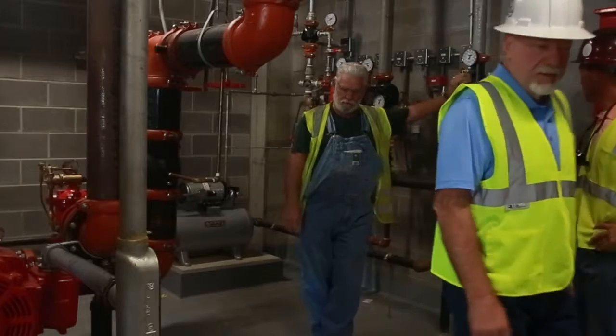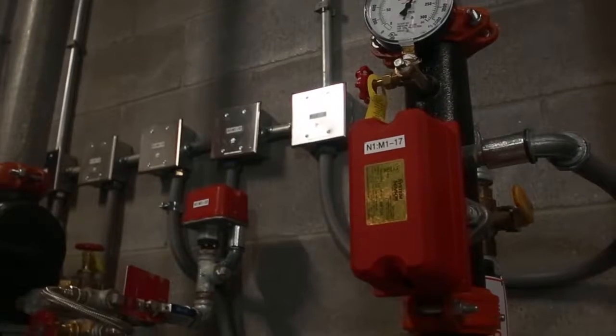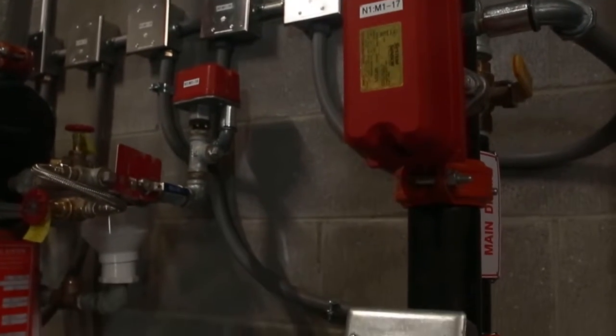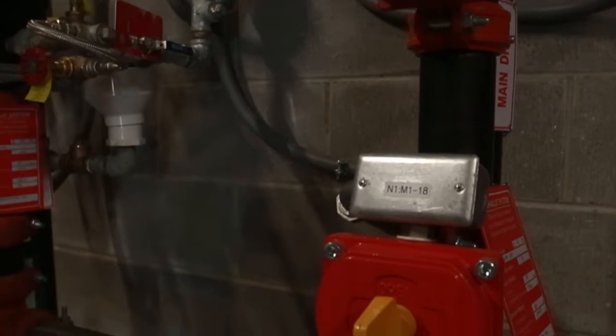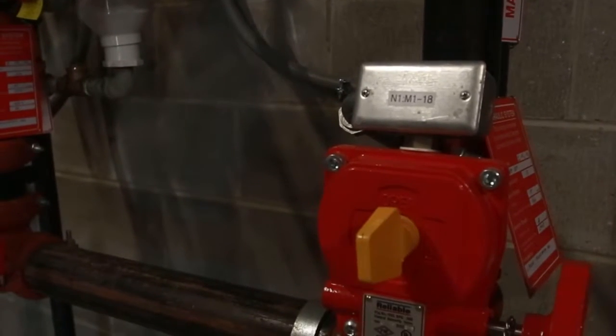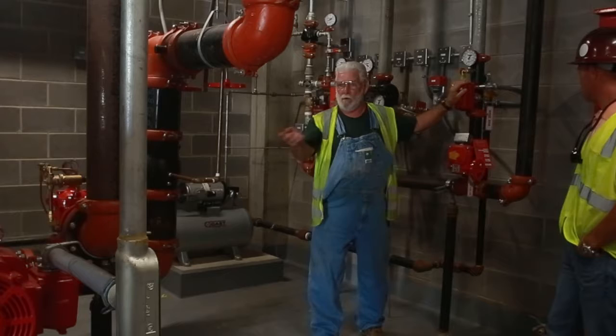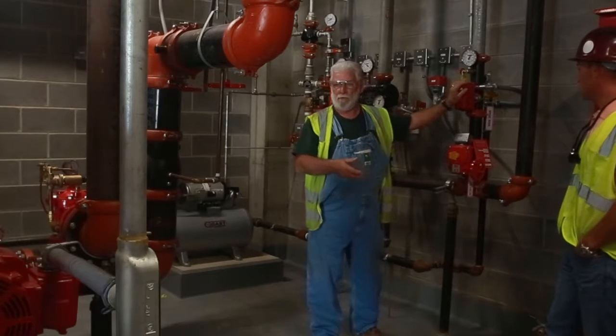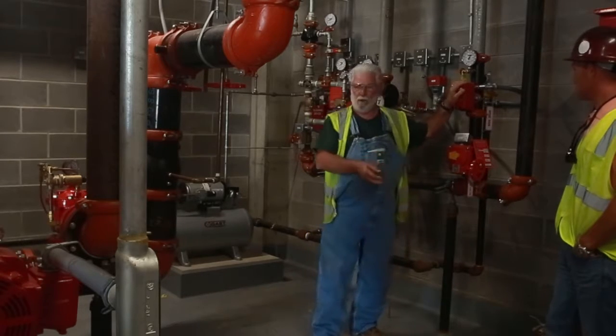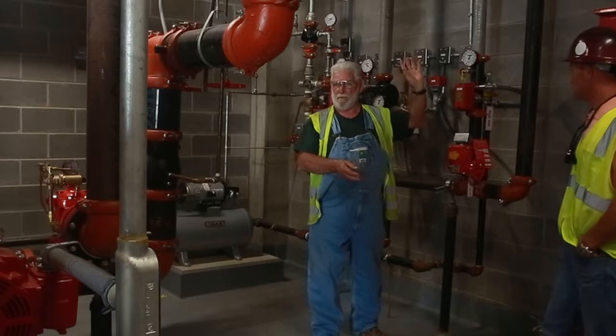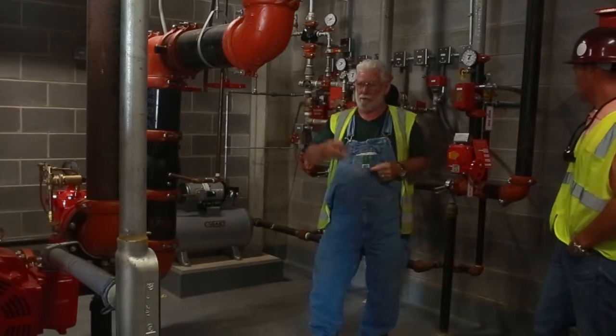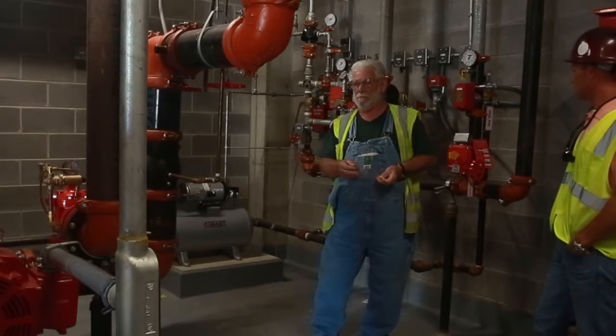That note, I guess. This is the wet system. Like I said, it covers the chill water room and the offices. And it's just a basic flow switch and a drain. That's all it is. Flow water, get it on, and then when you turn the water off, fill the system back up, fix whatever's wrong, reset the panel, and set it right back up.